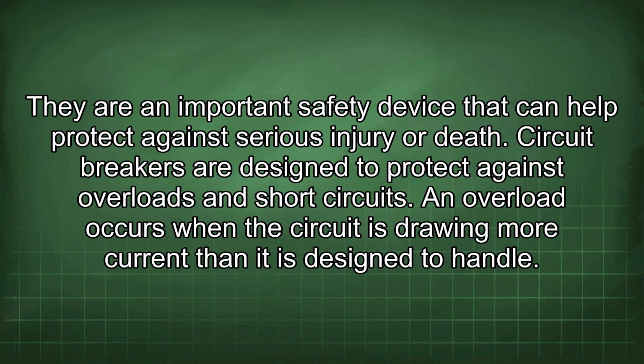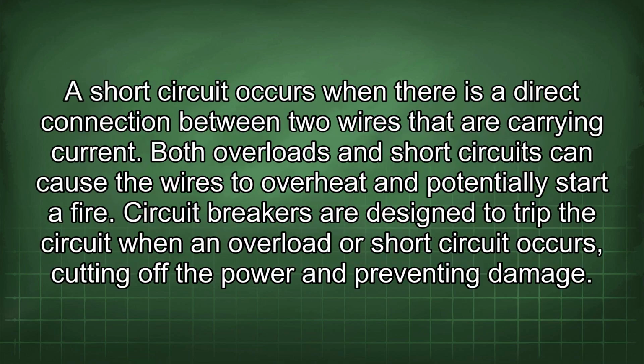Circuit breakers are designed to protect against overloads and short circuits. An overload occurs when the circuit is drawing more current than it is designed to handle. A short circuit occurs when there is a direct connection between two wires that are carrying current. Both overloads and short circuits can cause the wires to overheat and potentially start a fire.